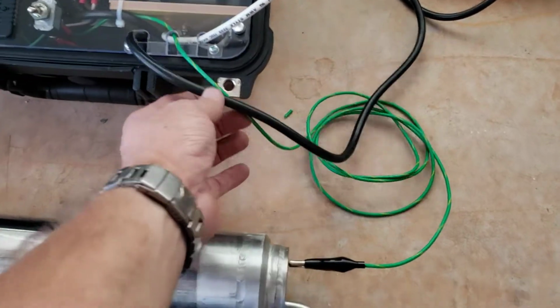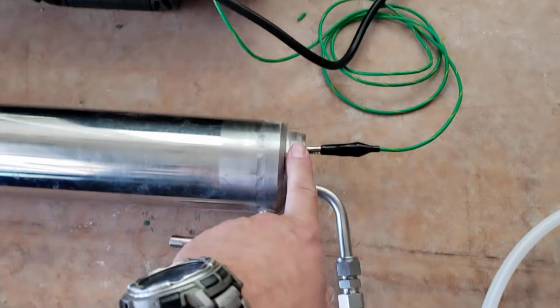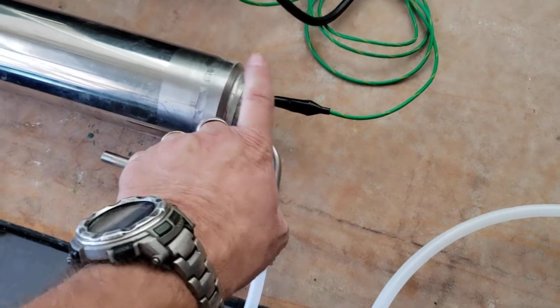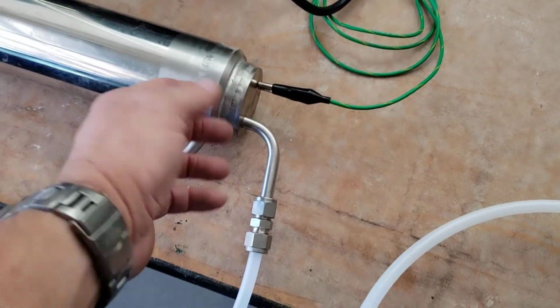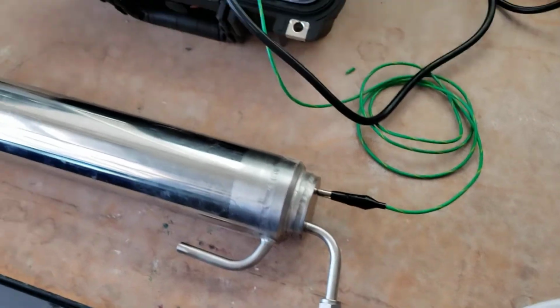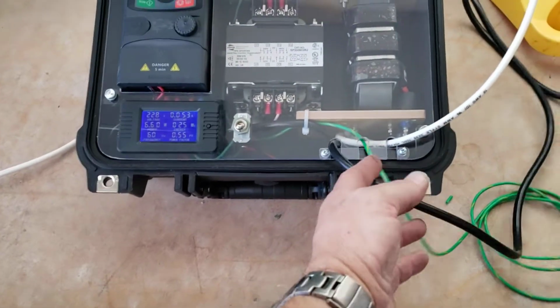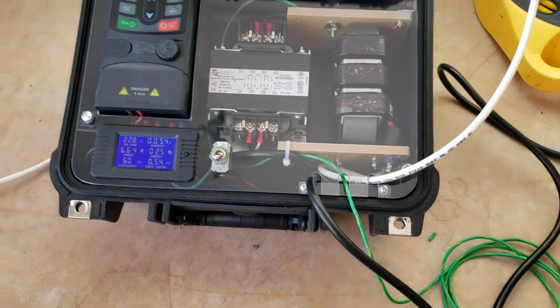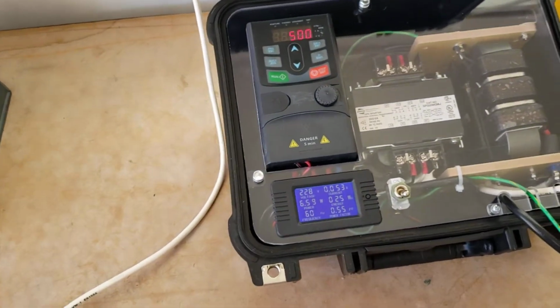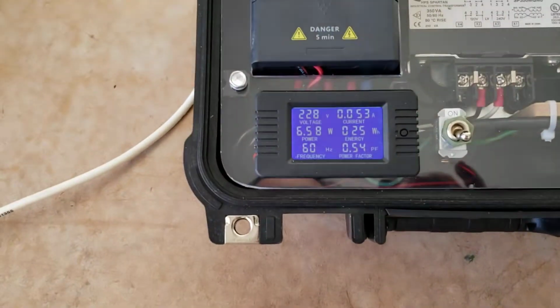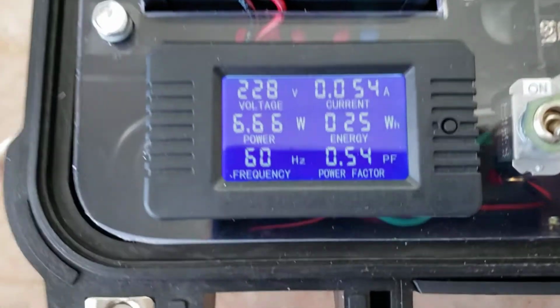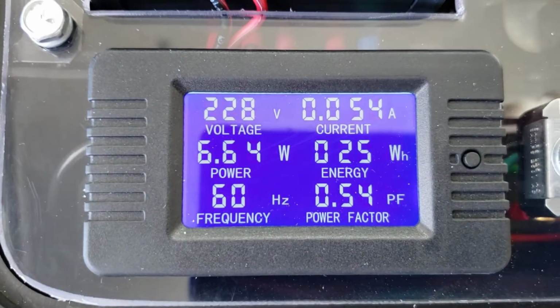Take the ground wire from the test box, hook that up to the chassis ground so that it's grounded to the cell. This can be on a grounding bar or directly to the cell itself. Then you're going to plug in the test box to a 115 volt outlet. Again, make sure the toggle switch is off when you start this. You do have 230 volts because we have a step-up transformer in here to feed the power supply.